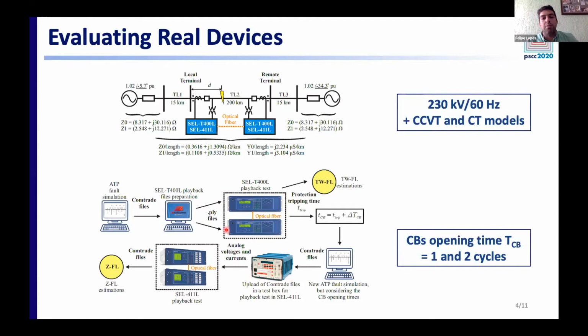into real-time domain relays, from which traveling wave-based fault location estimations were obtained, and also the high-speed protection tripping times, which were combined with different circuit breaker opening times, which are taken here as 1 and 2 power cycles, considering some recent reports regarding high-speed circuit breakers.